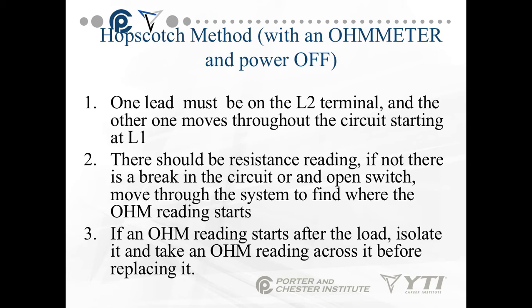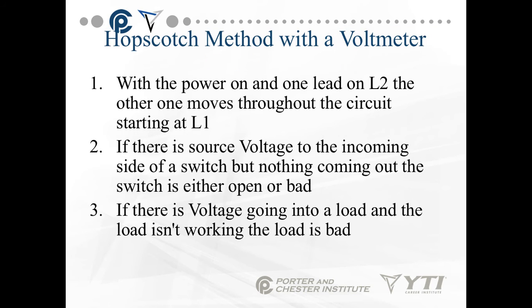If an ohm reading starts after a load, isolate it and take an ohm reading across it before replacing it. With the hopscotch method using a voltmeter, with power on, carefully move one lead onto the L2 terminal and the other through the circuit starting at L1. If there's source voltage to the incoming side of a switch but nothing coming out, that switch is either open or bad — and this includes contacts, pressure switches, or anything that controls the flow of current. If there's voltage going into a load and the load isn't working, the load is bad.